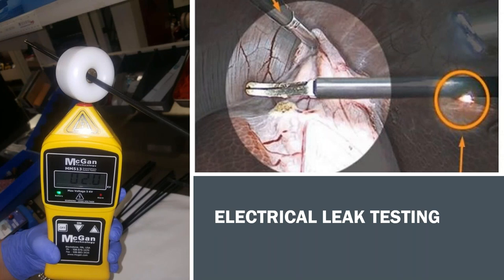It's a must-have, number one, because it's required by IFUs, but also because there's a significant risk to our patient should they get burned by a stray electrical current leaving a compromised area of the instrument.